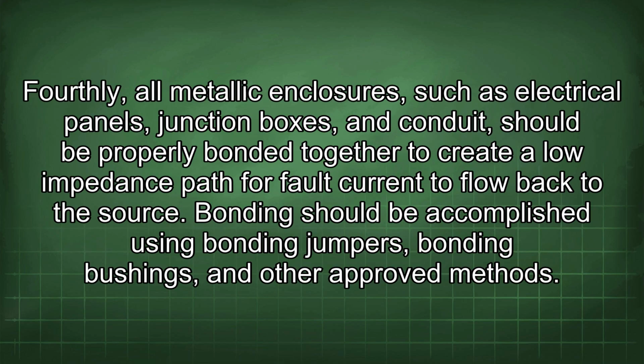Fourthly, all metallic enclosures, such as electrical panels, junction boxes, and conduit, should be properly bonded together to create a low impedance path for fault current to flow back to the source. Bonding should be accomplished using bonding jumpers, bonding bushings, and other approved methods.